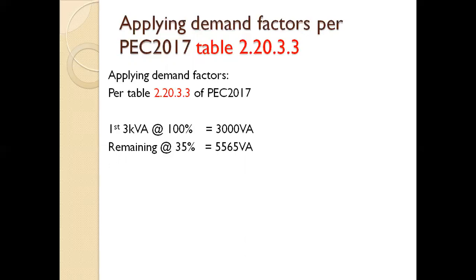So, 18.9 minus 3 is equal to 15.9. Times 0.35, we have 5.565 kVA. That is the application of the remaining 35%. Then you sum it up. Its total demand load is 8.56, or 8.565 kVA.